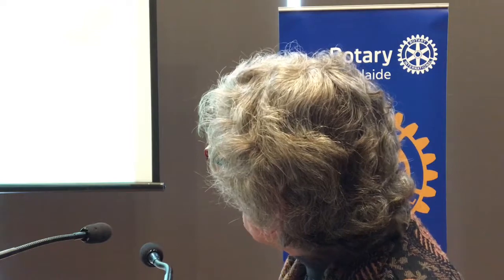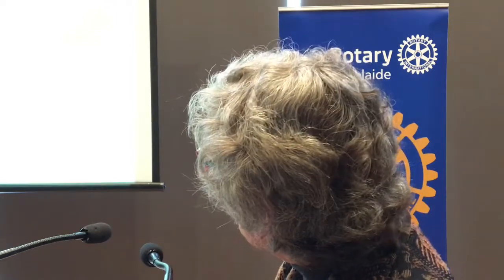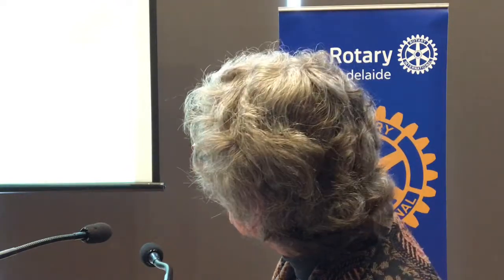This has all been rectified, but on the day, there wasn't all that much knowledge of what the settings were. So there, 456 megawatts went down, the interconnector got overloaded, everything happened within 2 minutes, so not enough time for extra gas to be put online, and so there was a blackout. Then to start up from a black start, you need some fossil fuel generators to start it up. Those generators that were allocated to do that actually didn't work, and so it had to be fixed by the interconnector.